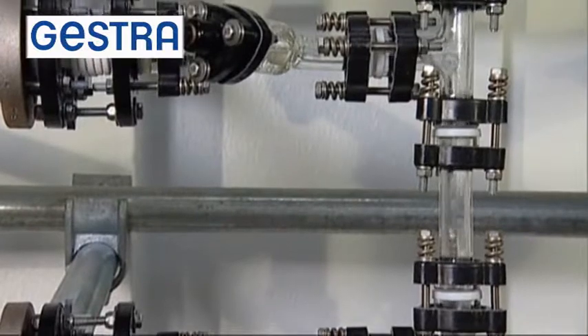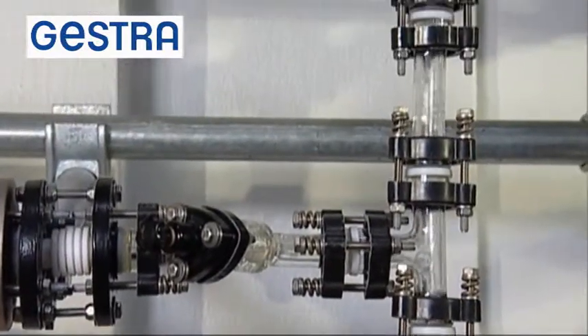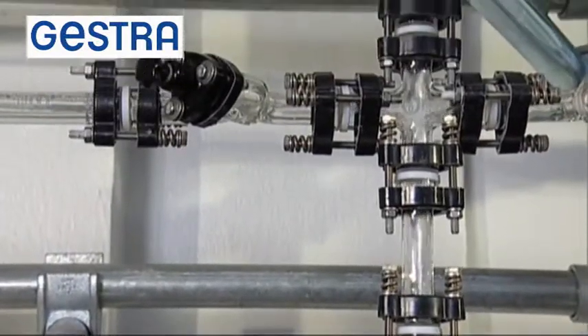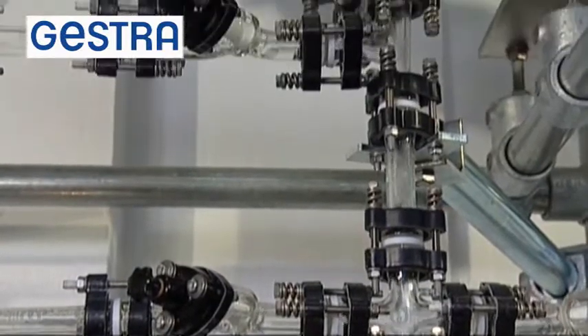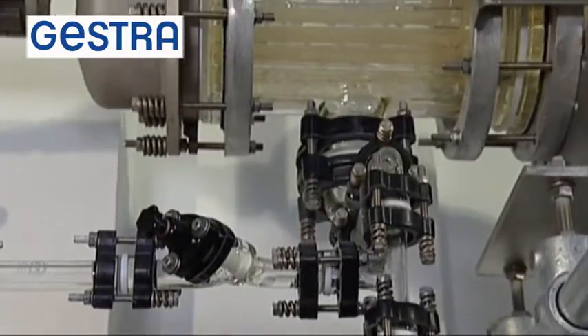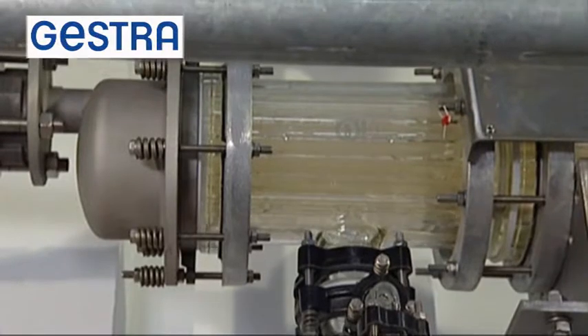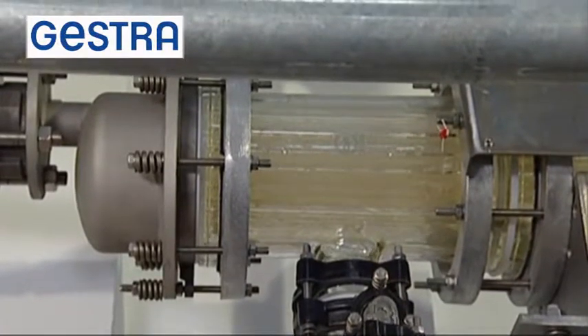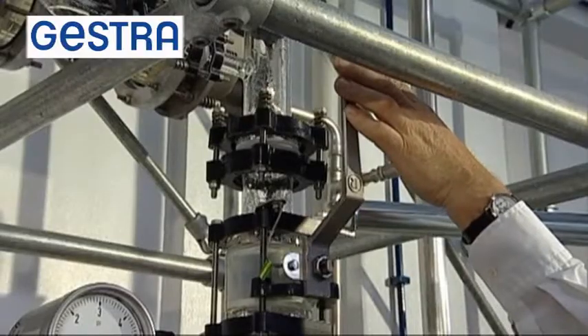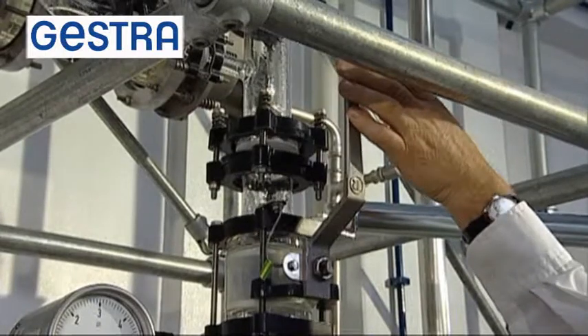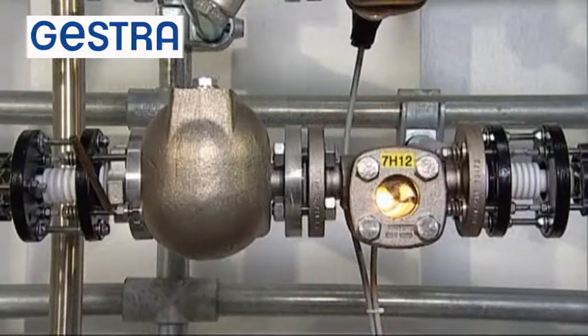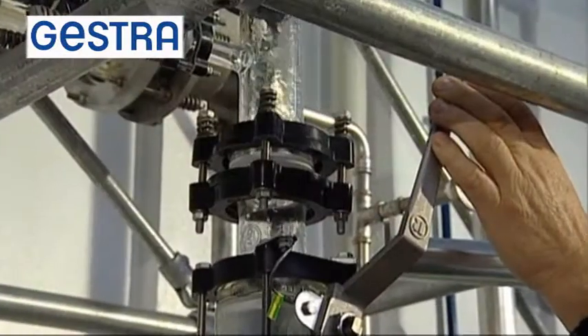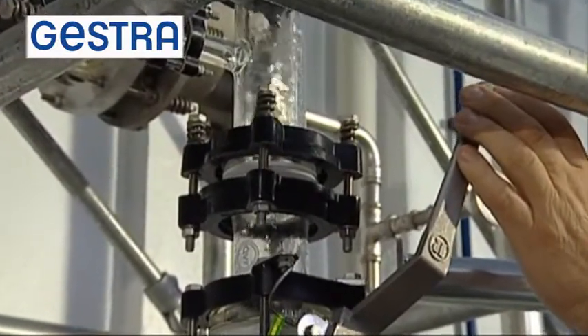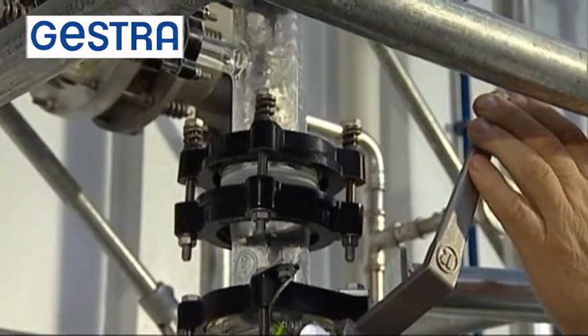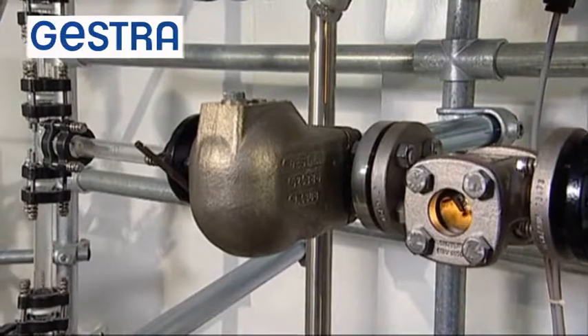Even at very low differential pressures, ball float traps are able to discharge large quantities of condensate. If the steam trap is sized correctly, the heat exchanger will always be drained without any banking up. This in turn will ensure that the product is always heated correctly. If the steam is controlled and the steam pressure varies as a result, this will have hardly any influence on the condensate discharge, which will still be controlled solely by the level in the trap, independently of pressure and temperature.